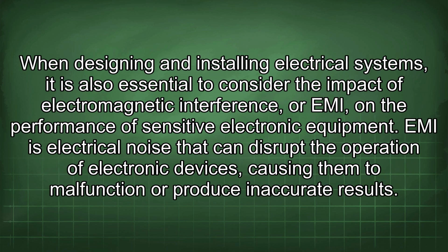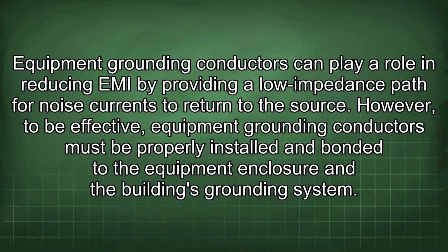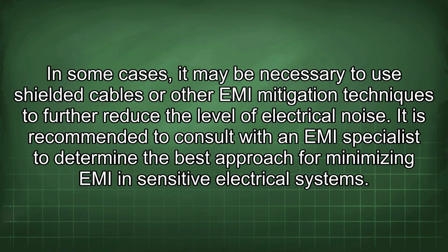When designing and installing electrical systems, it is also essential to consider the impact of electromagnetic interference, or EMI, on the performance of sensitive electronic equipment. EMI is electrical noise that can disrupt the operation of electronic devices, causing them to malfunction or produce inaccurate results. Equipment grounding conductors can play a role in reducing EMI by providing a low impedance path for noise currents to return to the source. However, to be effective, equipment grounding conductors must be properly installed and bonded to the equipment enclosure and the building's grounding system. In some cases, it may be necessary to use shielded cables or other EMI mitigation techniques to further reduce the level of electrical noise. It is recommended to consult with an EMI specialist to determine the best approach for minimizing EMI in sensitive electrical systems.